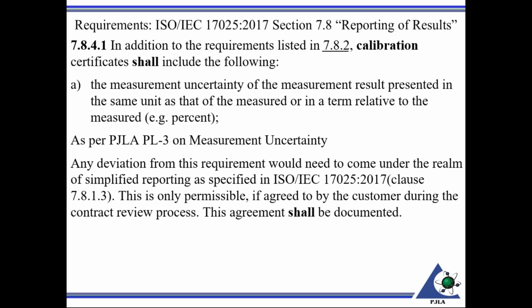And this comes out of PL3. This is our policy, and this shall be documented. So unless otherwise specified under for calibration, the uncertainty is required to be put on reports. And if it's not, it has to be customer driven, customer specified, and a record needs to be created during contract review, to have that agreement in writing.